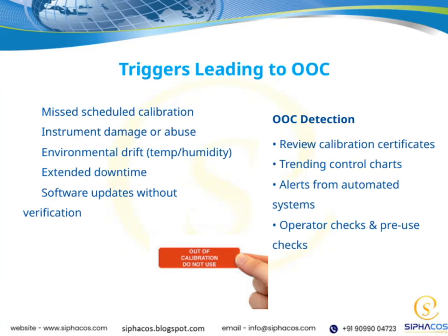Now, let's talk about OOC detection, or out-of-calibration detection. One of the first steps is to review calibration certificates regularly, making sure everything is up to date and valid.